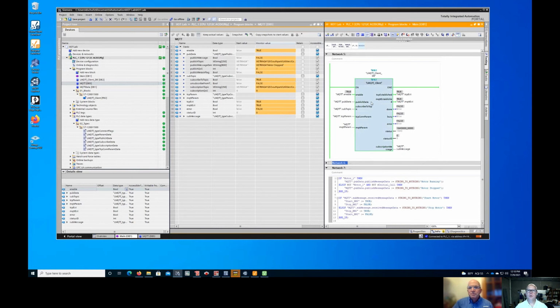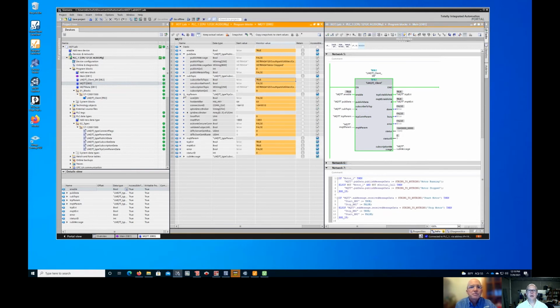When you first drag one of your function blocks out, the second thing you're going to want to do is it's now going to throw this data block up here. I'm sorry, that's what Siemens calls everything, a block. Then you're also going to have to create another data block, which is this MQTT one, and that's where I have all of this configuration done. So you have to get in and address what all your parameters are. This is where you're going to identify, okay, am I using a fully qualified domain name? What's my hardware identifier? Again, the Automation Station video will walk through some of that. Connection ID, and then you have to set up your broker and that type of thing through here.